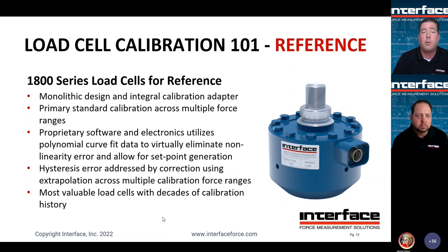And then we use a proprietary software set and electronics that utilize the polynomial curve fit data. This helps us eliminate as much as possible the nonlinearity error, and also allows us to generate some different calibration points as needed for customer and production requirements. And we address hysteresis error by using multiple descending force calibration ranges and extrapolating across the two.